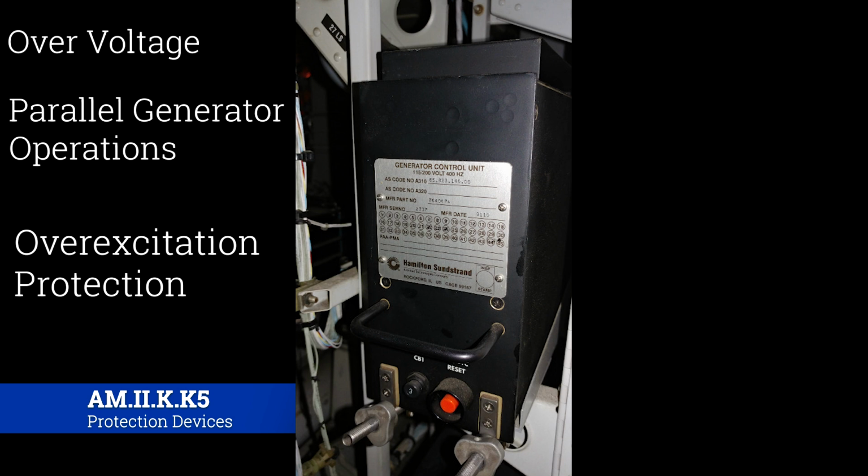Okay, overexcitation protection. This is actually a really interesting one. When you have multiple generators that are working together, and one of them fails, then all of a sudden another GCU could say, like, hey, look, our power's fallen off. Now we need to increase the power to compensate for what's been lost. And effectively, you could have one generator doing the job of two generators. Well, that one generator is not really built for that. Just like with people, if you have one guy on a team that's overworking to compensate for other people not doing their job, that guy will burn out.